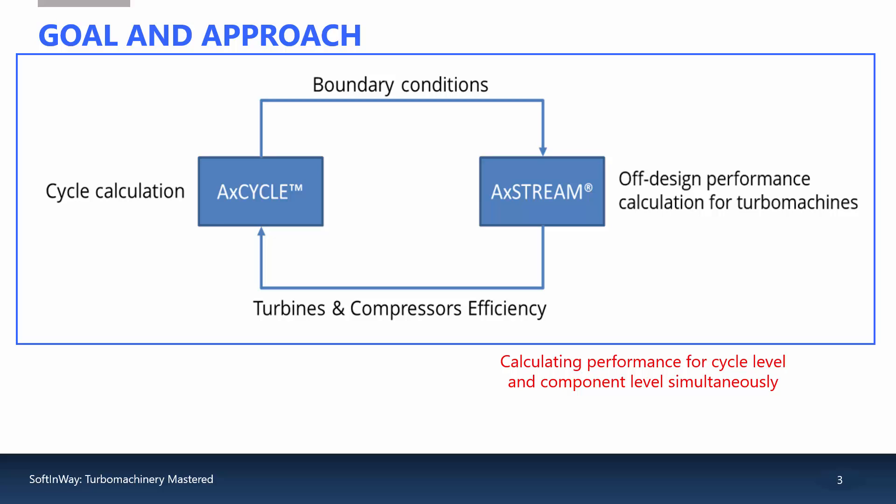Here we want to simulate off-design conditions for a given system at different part load points. For each point, we are not only analyzing the performance of the cycle, but we are accounting for the involved turbo machine's performance, iterating automatically until there is a match between component efficiencies in the cycle and the detailed turbo machine simulations.